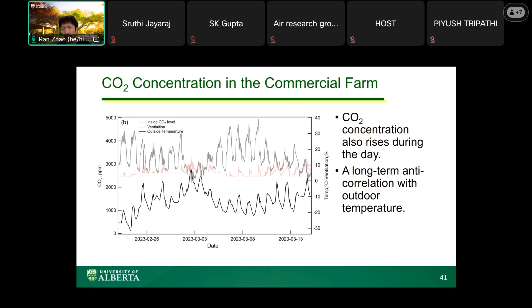We also saw a general anti-correlation with outdoor temperature, shown by the darker black line on the right axis - you can see temperatures like minus 30 degrees, which isn't a mistake, it's Canada, so that's the real outdoor temperature. Day to day there's a diurnal trend, but over this span of three weeks or so, there's a general anti-correlation between indoor CO2 and outdoor temperature. That's because when it's cold, the ventilation rate in the farm is automatically lowered to maintain temperature, whereas when it gets milder, the ventilation rate goes higher. The ventilation rate is the red line here, which leads to lower CO2 concentration. So we were able to see this correlation between outdoor temperature, ventilation rate, and CO2 concentration in the farm.